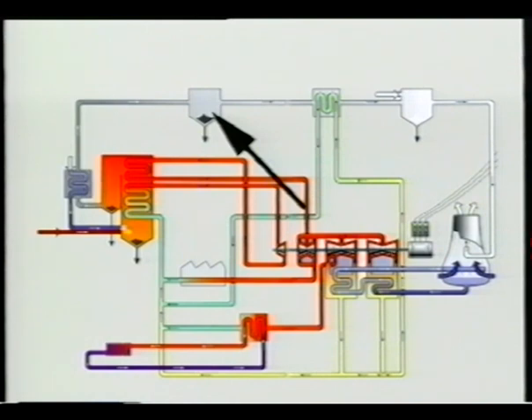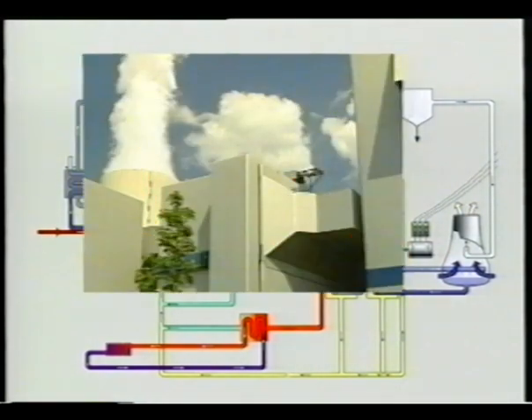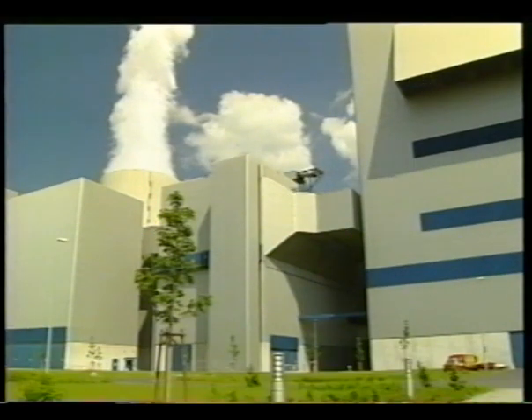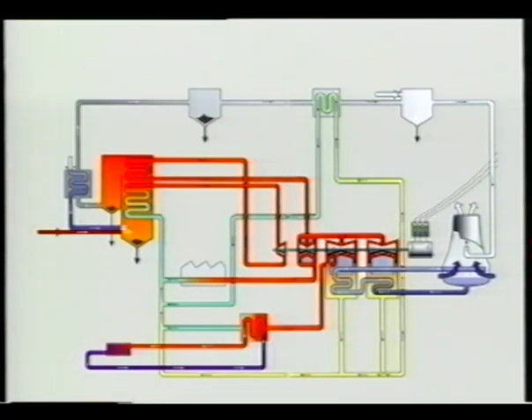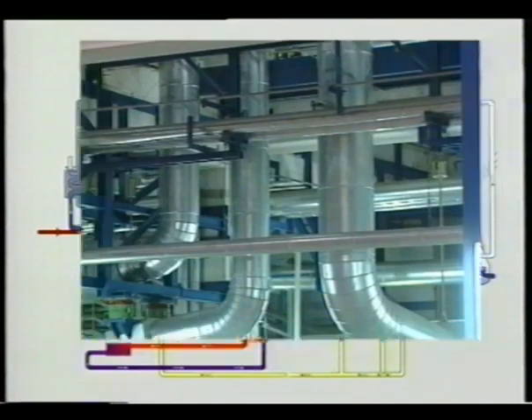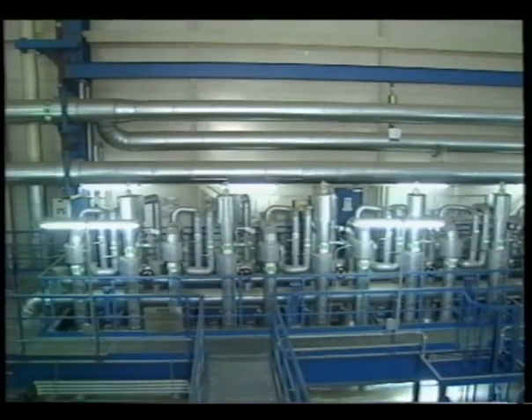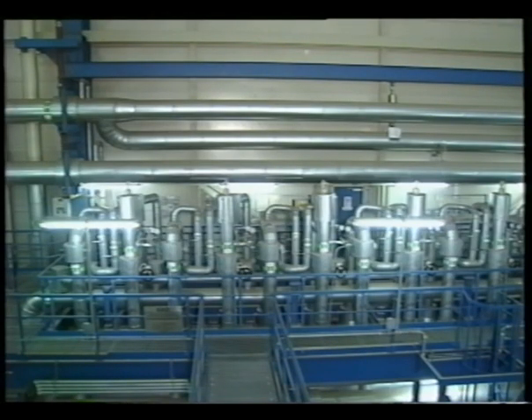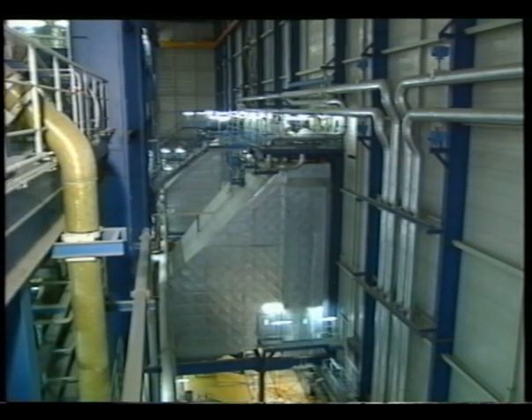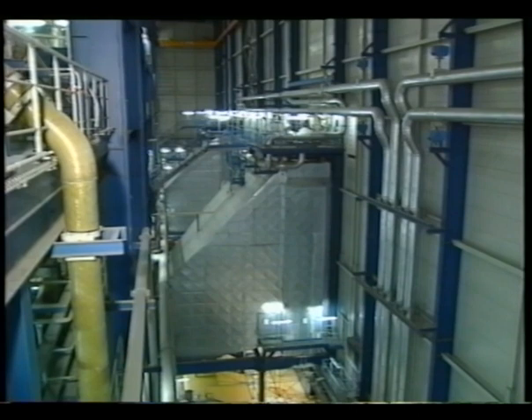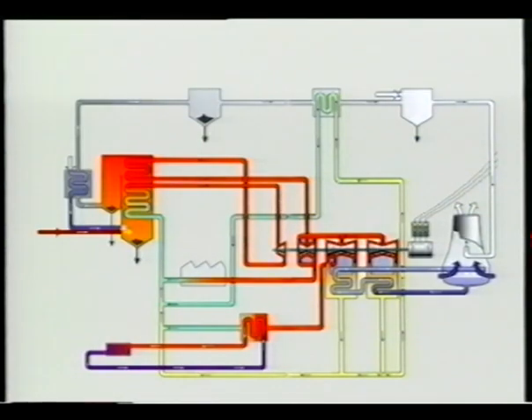99% of the dust is then extracted from the flue gas through the electrofilter. The induced draft fan forces the flue gas into the heat exchanger. At that point, it is at a temperature of 170 degrees Celsius. Here, the rest of the heat is extracted for the preheating of the feed water. The flue gas cools by 130 degrees Celsius.